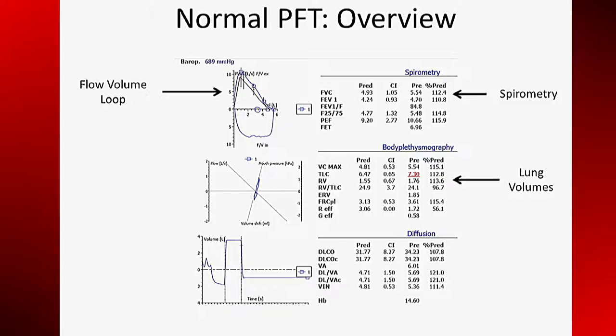Next are lung volumes. These numbers are derived from pressure measurements taken from a mouthpiece and body box. The procedure is called body plethysmography. An alternative method used by less expensive equipment derives lung volumes from helium dilution. Last are the diffusion measurements. These numbers are derived from measurements of carbon monoxide.